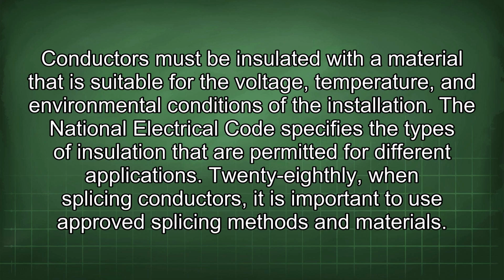27thly, another important consideration is the type of insulation used on the conductors. Conductors must be insulated with a material that is suitable for the voltage, temperature, and environmental conditions of the installation. The National Electrical Code specifies the types of insulation that are permitted for different applications.